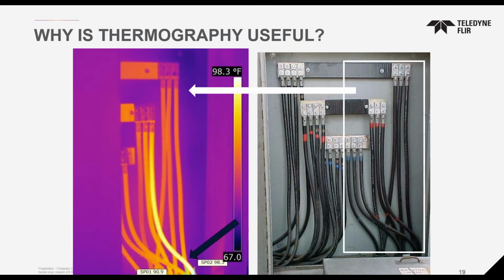Here's some more cables in this junction box. The load current was almost equal across these nine different cables, except for this one right here in the middle. Similar to the last image, you can see as we go down this cable the color is getting brighter and brighter, indicating that it's getting hotter and hotter.